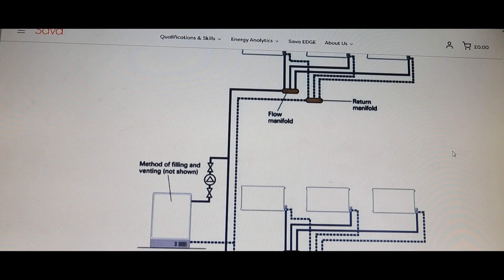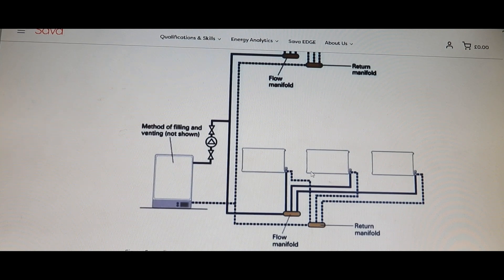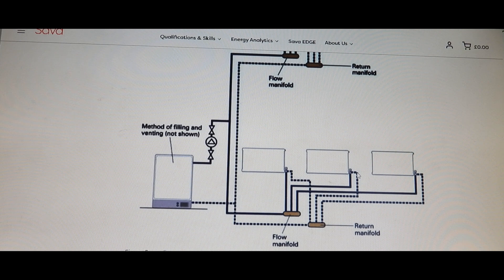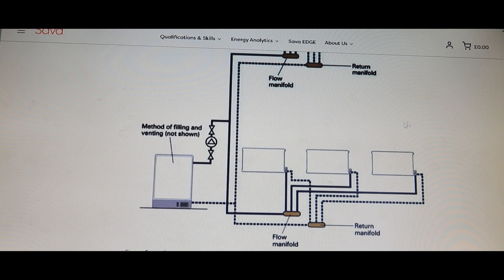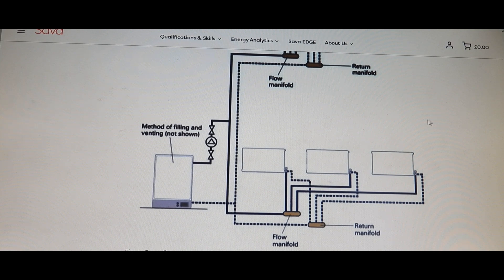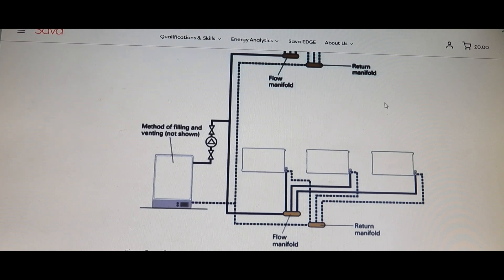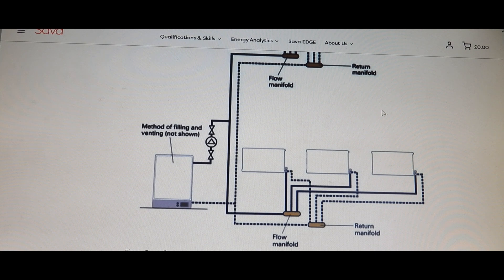The other things that can happen with microbore: I've had pipework under radiators that often go under rather than going to a two-pipe valve, and I've seen hoovers have knocked and marked them and put dents into the tube. They don't realize they're there because they're under the radiator. The hoover goes under and bang, there's a dent in there. So one of the rads stops heating up and you think it's blocked up, but it's not, it's a dent.